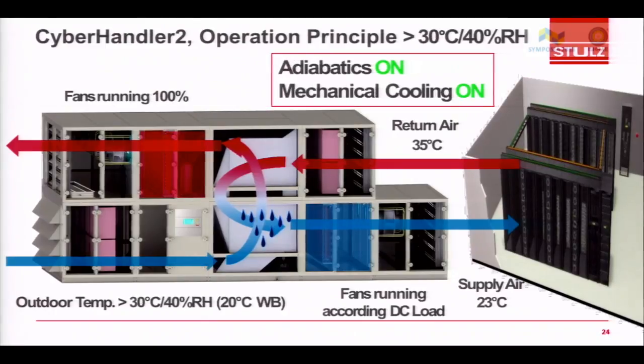Now next is your temperature goes above 30 degrees Celsius. So your adiabatics on, mechanical cooling on. There is the condenser, there is the evaporator. I hope this slide is clear because the confusion will happen about where the air is moving, where the air is going. So this is moving towards the data center, this air is coming back, passing through the air heat exchanger, and the cooling is happening. So minimal usage of the compressor has to be done when we cool data centers.